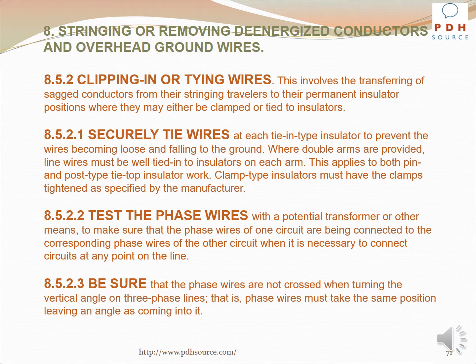With regard to clipping in or tying wires, this involves the transferring of sagged conductors from their stringing travelers to their permanent insulator positions, where they may either be clamped or tied to insulators. Securely tie wires at each tie-in type insulator to prevent the wires becoming loose and falling to the ground. Where double arms are provided, line wires must be kept tied in to insulators on each arm. This applies to both pin and post type tie-top insulator work. Clamp type insulators must have the clamps tightened as specified by the manufacturer.